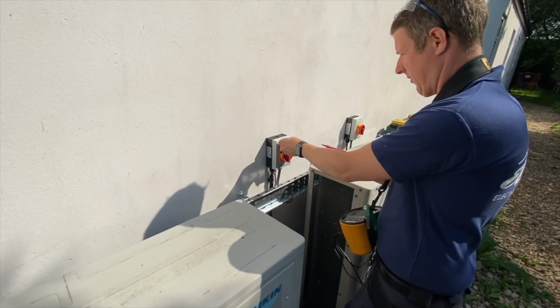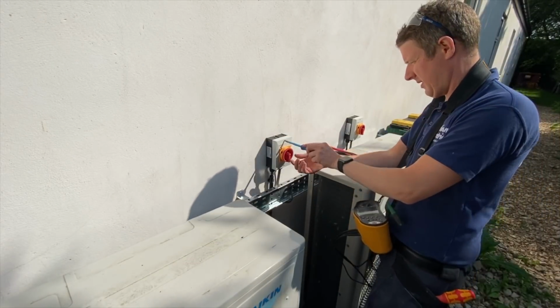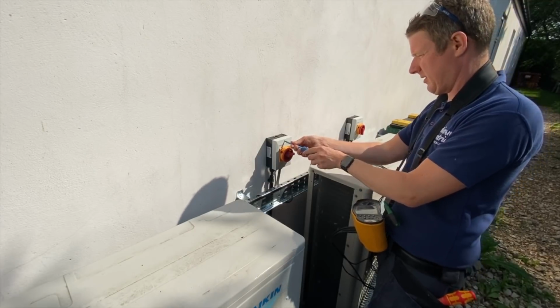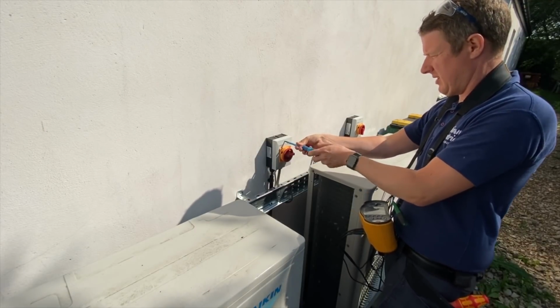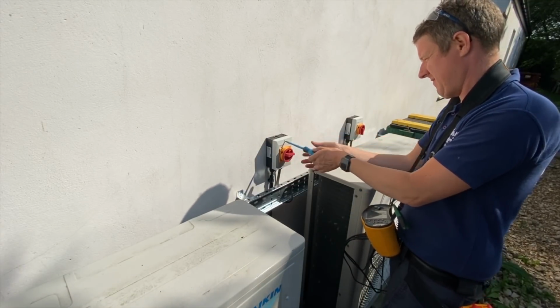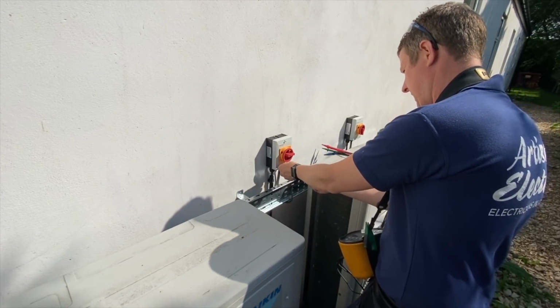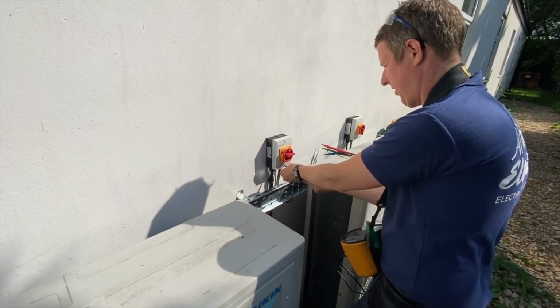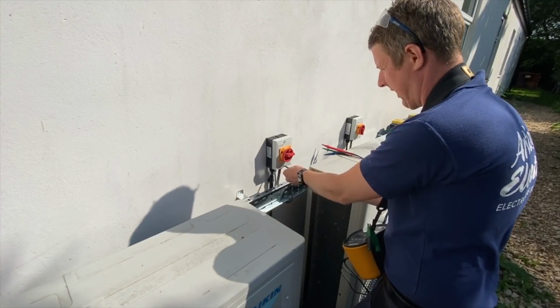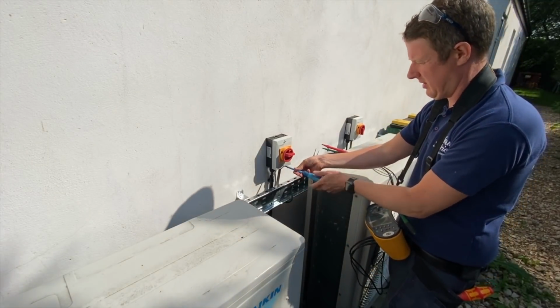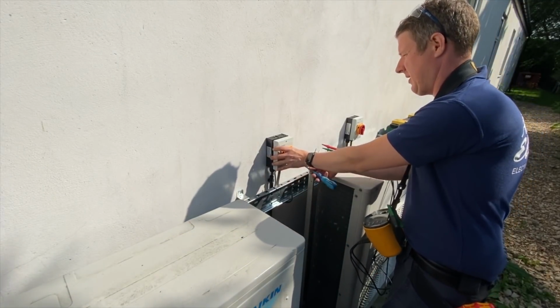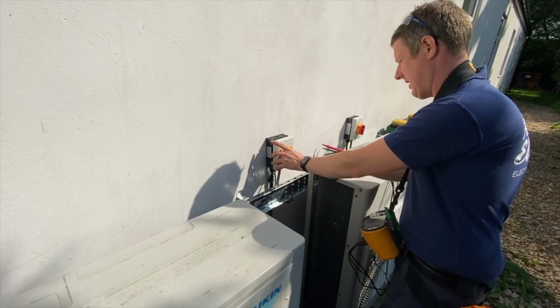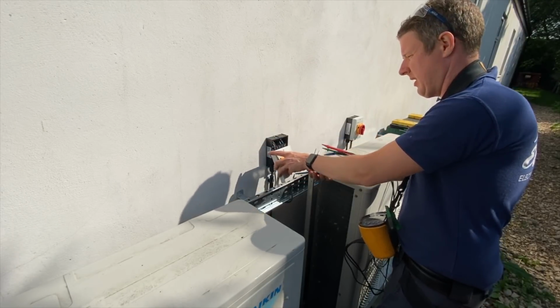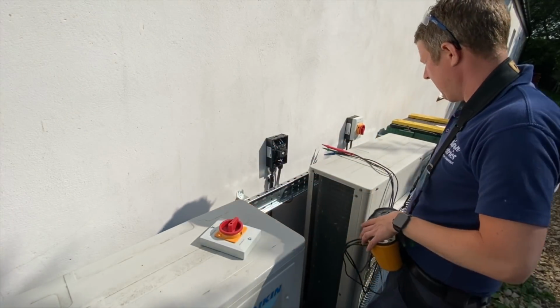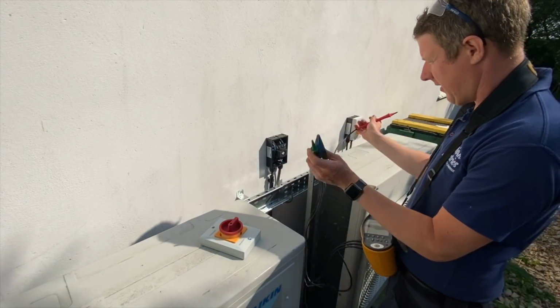So we're going to take the cover off. Turn the isolator off first, so the outgoing side is dead at least. Obviously earth loop impedance tests have to be done live, so you have to be very careful and make sure that you're using the correct test leads that are acceptable for testing on live.